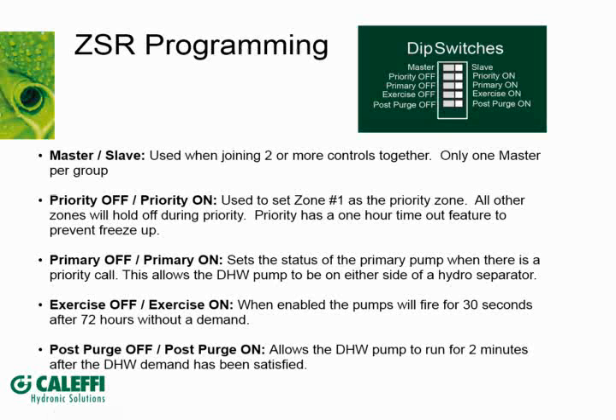There is a 1-hour timeout feature. So how that works is, if priority calls and it's there for longer than 1 hour, after 1 hour the control will go out and look if there's a demand by any of the other space heating zones. If there is a demand, it will go out and satisfy all of those space heating demands. Once those are satisfied, it will then go back to the domestic hot water, and the 1 hour timer resets itself. So that way we'll prevent the freeze up. Let's say you got an aquastat that's stuck. It's not going to freeze up your house because of that stuck aquastat.